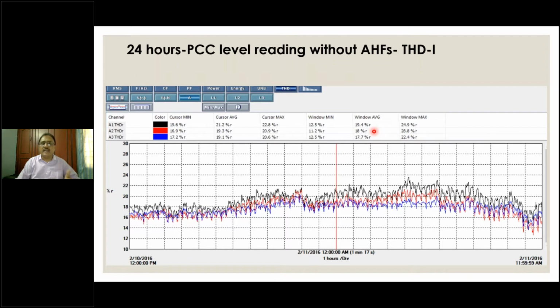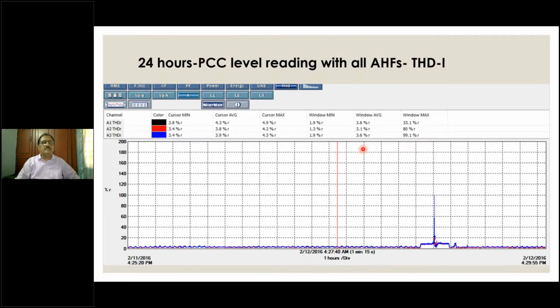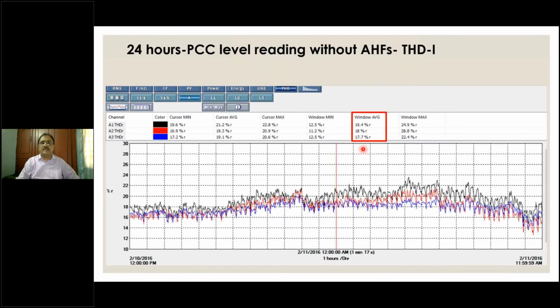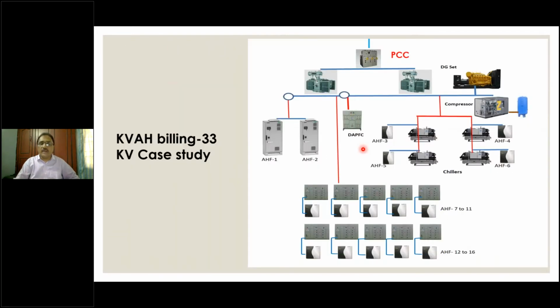But in Andhra, they had kVAH billing. This is bordering Chennai, Sri City, Andhra Pradesh. So what we did was we told the customer that this has to be brought down. And we also wanted to tell the customer what is the impact of this. So after we did the surveys, you saw this slide, we provided for each MCC 60 ampere active harmonic filter.